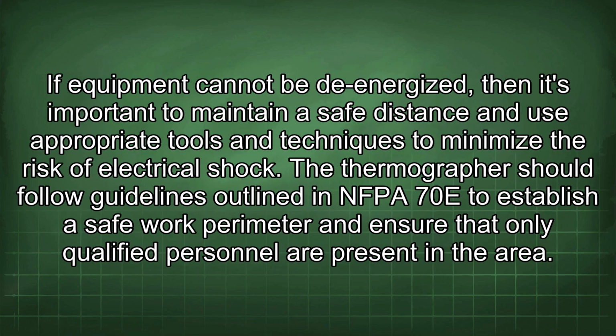If equipment cannot be de-energized, then it's important to maintain a safe distance and use appropriate tools and techniques to minimize the risk of electrical shock. The thermographer should follow guidelines outlined in NFPA 70E to establish a safe work perimeter and ensure that only qualified personnel are present in the area.